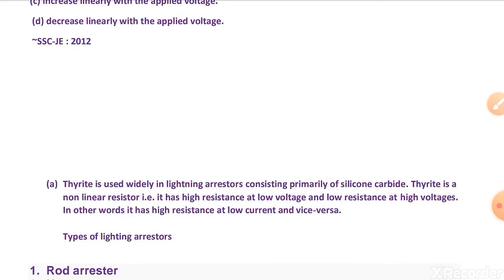Thyrite is used widely in lightning arresters, consisting primarily of silicon carbide. Thyrite is a non-linear resistor — it has high resistance at low voltage and low resistance at high voltage. In other words, it has high resistance at low current and vice versa.